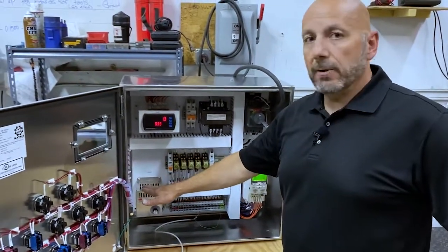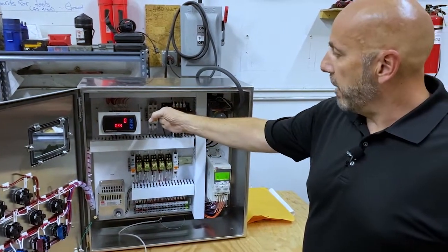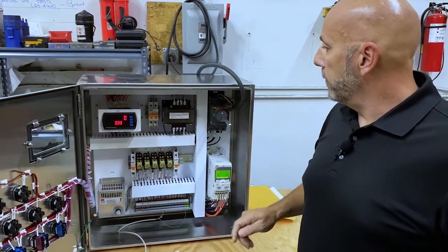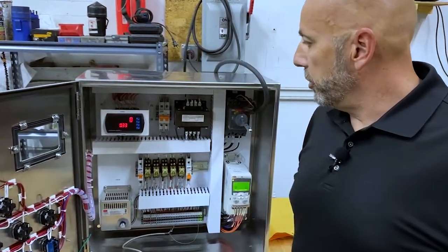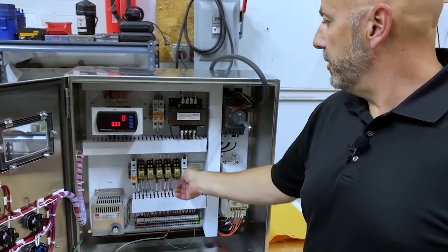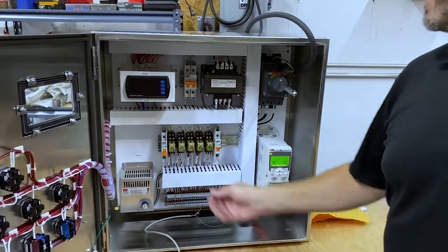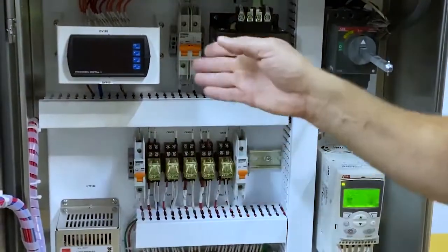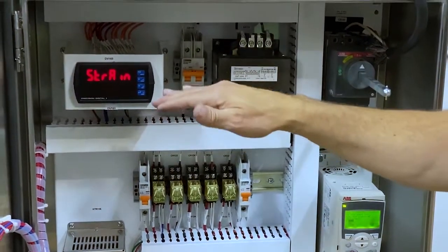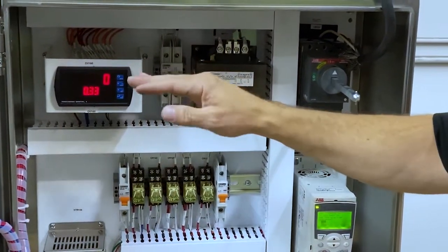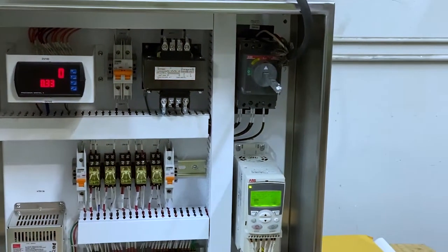We do have a condensate heater for you built in. Your disconnect switch. Main power disconnect for your lower 110 voltage. Breaker for your heater and the breaker for the strain gauge display. The strain gauge display is wired such that if we lose power to the display or the display fails, it will shut down the drive unit and not operate without torque protection.